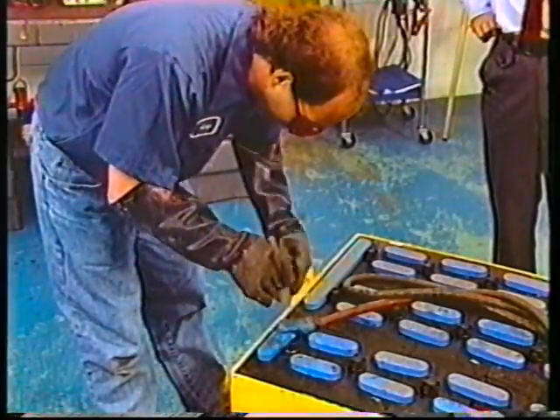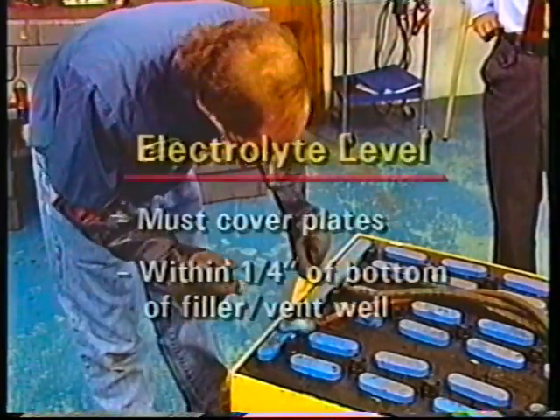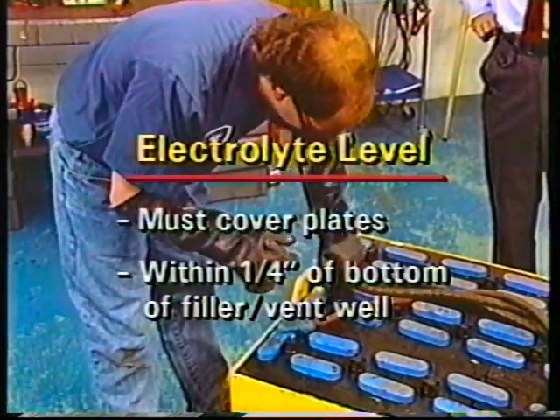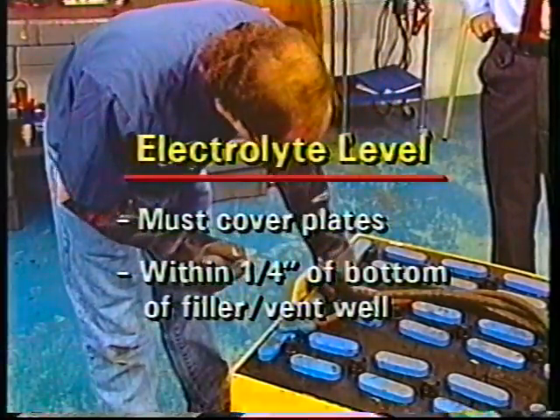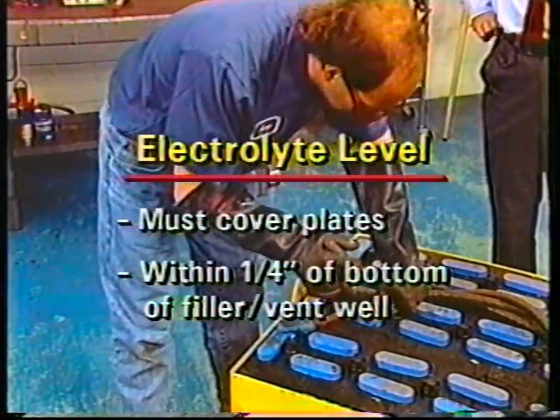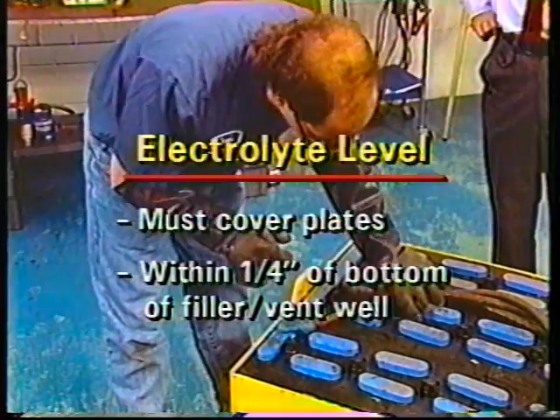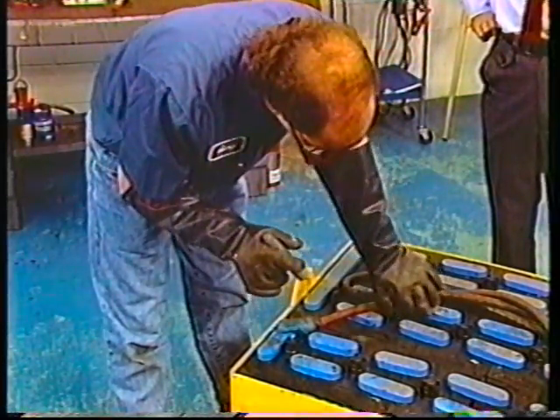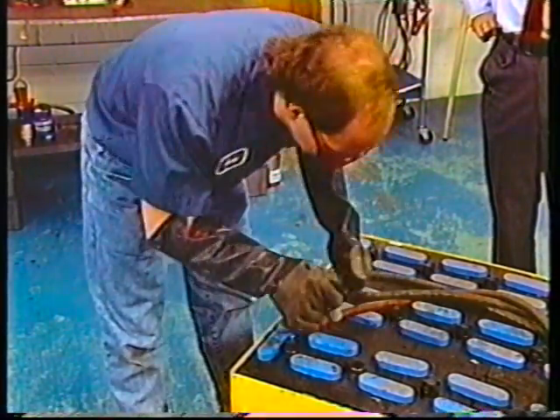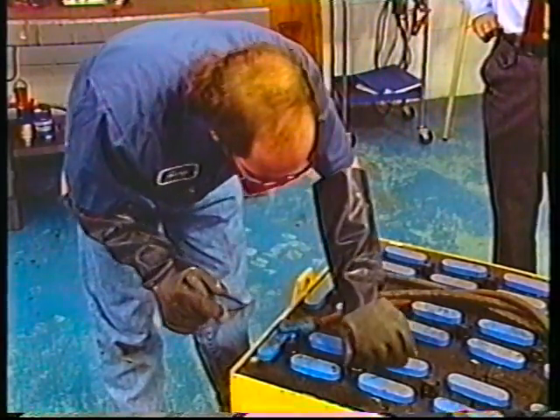Our final visual inspection is to check the electrolyte level and color in each cell of the battery. If the level is low, add distilled water, never tap water, and recharge the battery. The color of the electrolyte should be clear. If the electrolyte is dark, replace the battery and contact the battery vendor.